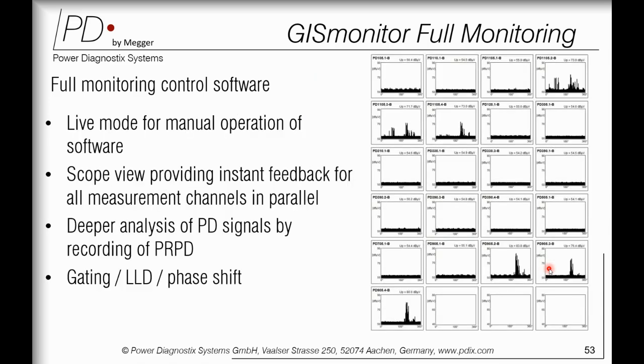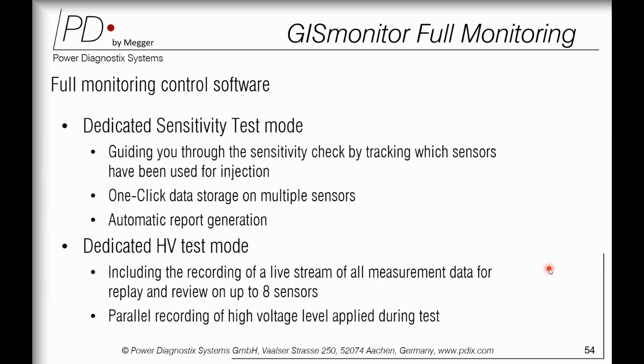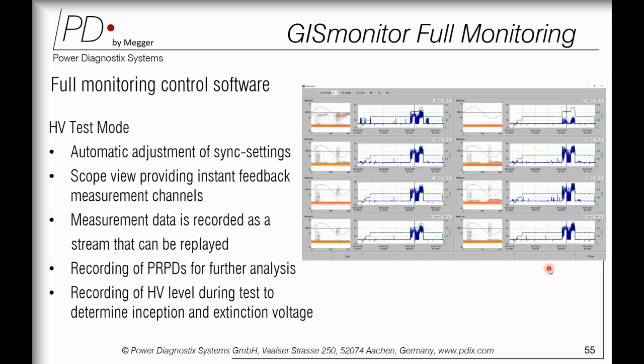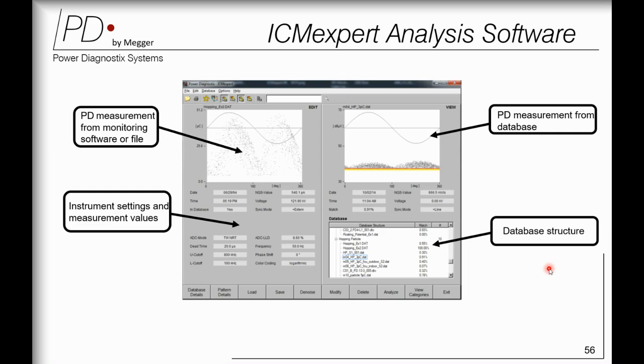It also has full monitoring control software, like live mode for operations, scope view, and deep analysis of PD signals by PRPD patterns and all. It also has dedicated sensitivity test modes and dedicated HV test modes. It also has full monitoring software device like HV test modes that we do for commissioning as well. And the main thing, we also have an ICM expert software.